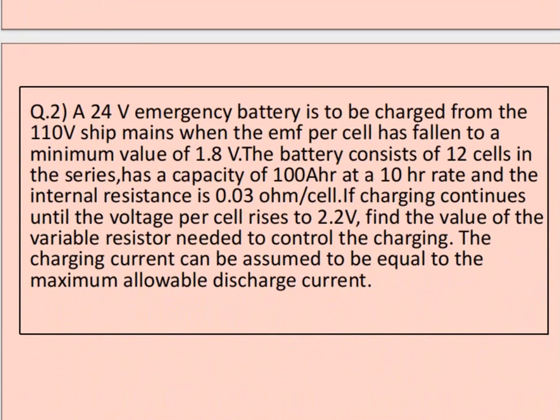Moving to question number 2: a 24-volt emergency battery is to be charged from a 110-volt supply when the EMF per cell has fallen to a minimum value of 1.8 volts. The battery consists of 12 cells in series, has a capacity of 100 ampere-hours at a 10-hour rate, and an internal resistance of 0.03 ohms per cell. If charging continues until the voltage per cell rises to 2.2 volts, find the value of the variable resistor needed to control the charging. The charging current can be assumed to be equal to the maximum allowable discharge current.